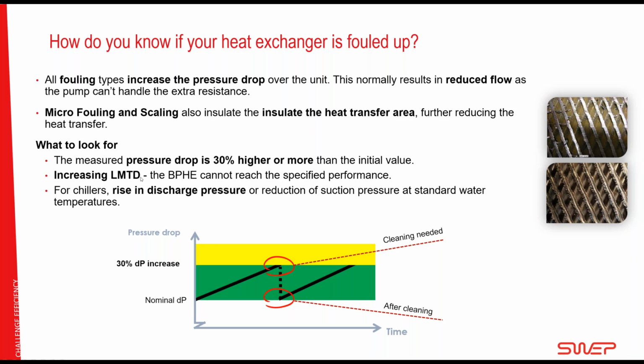So what to look for? If the pressure drop starts to go up, an indication that most plate type suppliers recommend is 30% higher than the nominal. But also if you start to measure an increased LMTD or a reduced efficiency, or if you have a chiller or a heat pump and you see a rise in the discharge pressure or a reduction of the suction pressure in the evaporator, that is a possible sign of fouling.